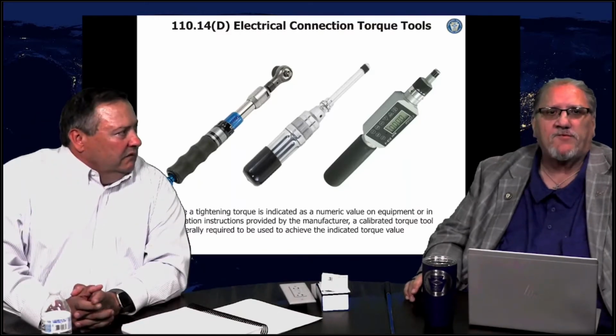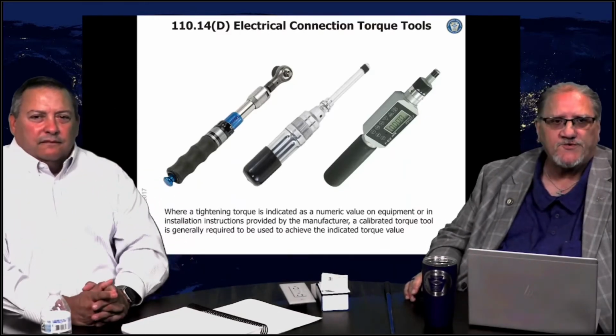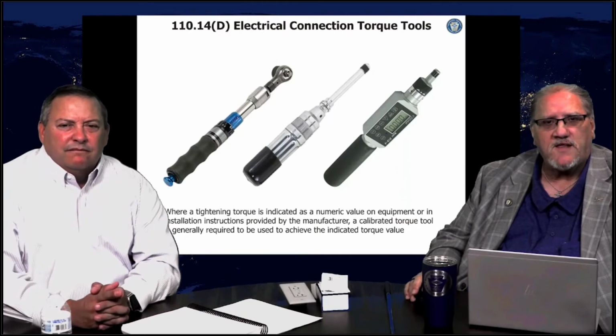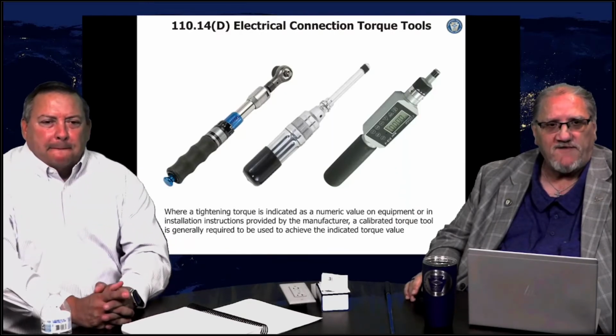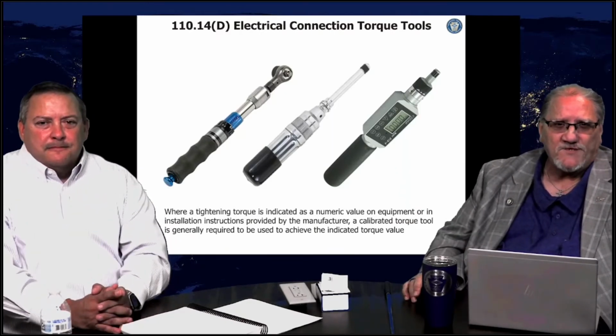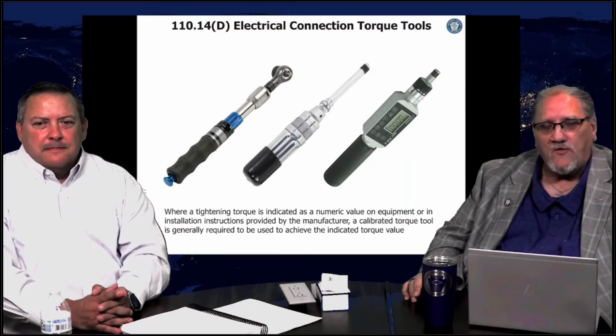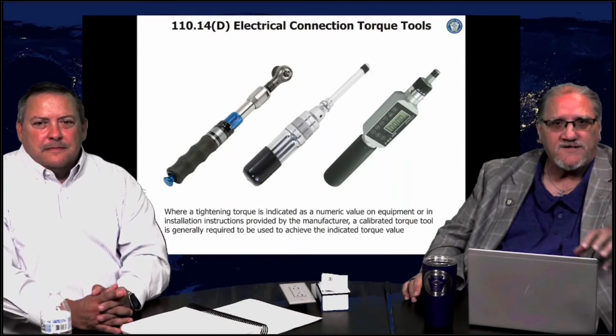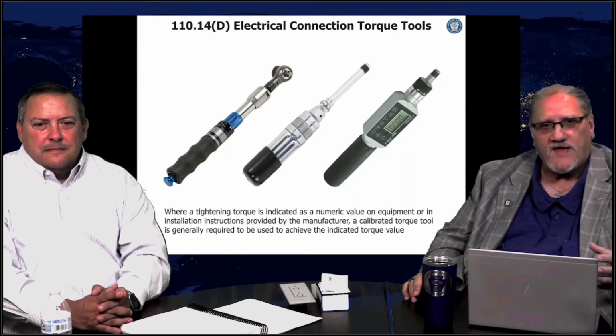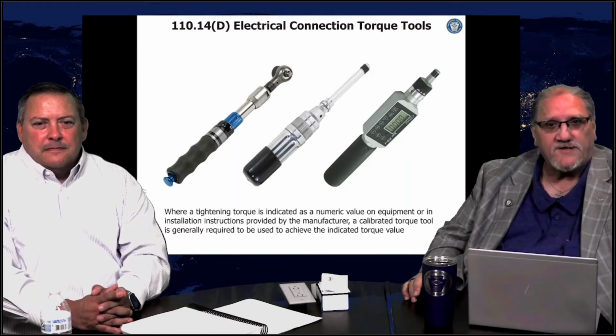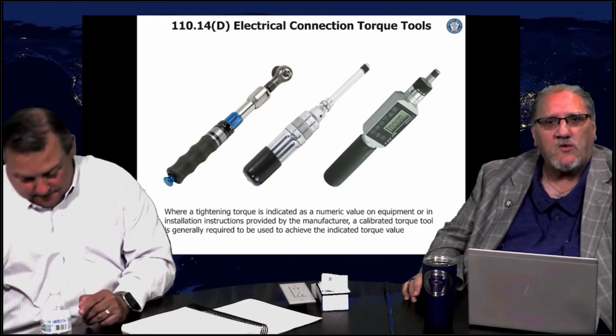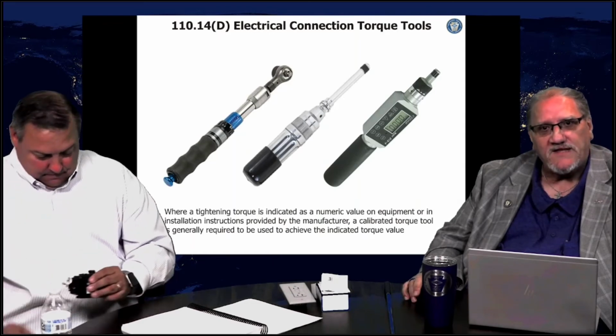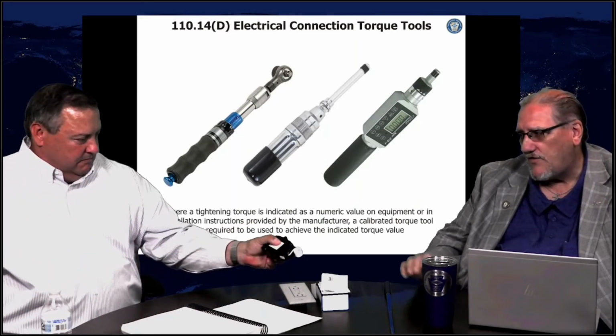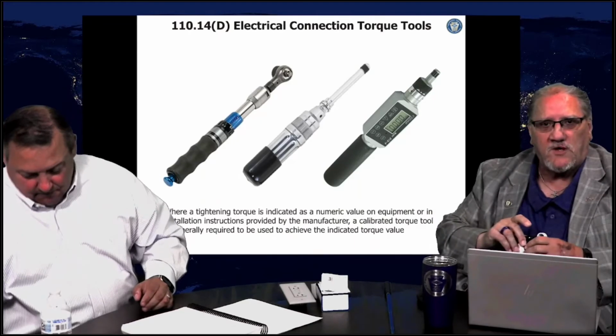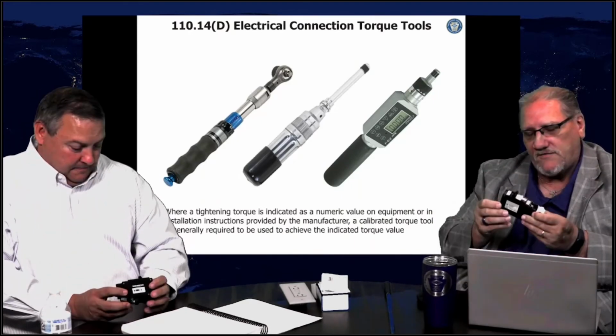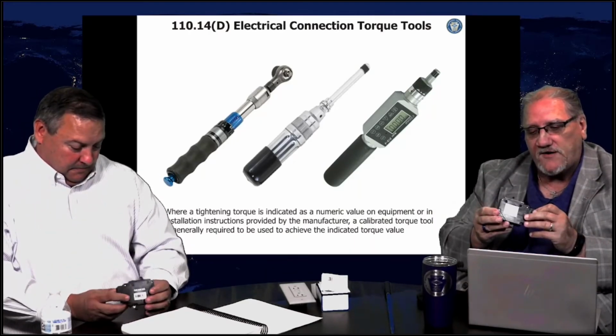There are three examples on the board there of tools that are capable of calibration and capable of achieving a numeric value. And for most equipment, receptacles, overcurrent devices, lugs in a panelboard, things like that, the manufacturer is going to mark either on that piece of equipment or in it somewhere the actual torquing values. Overcurrent device from Siemens right here.